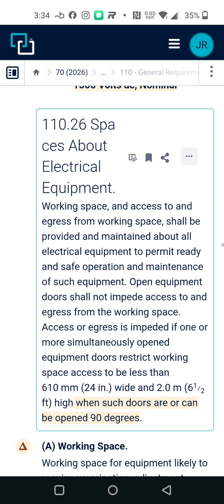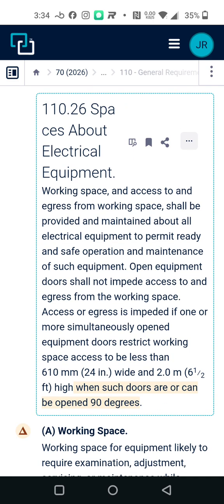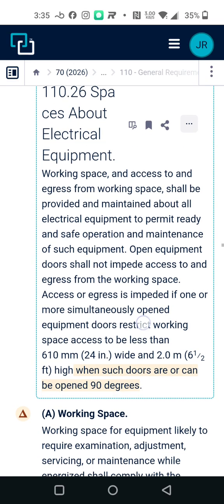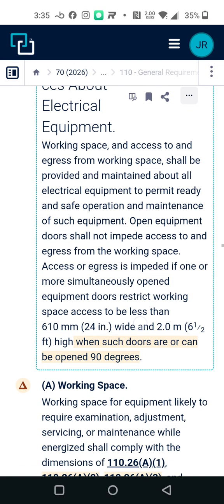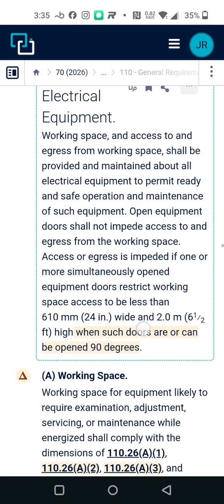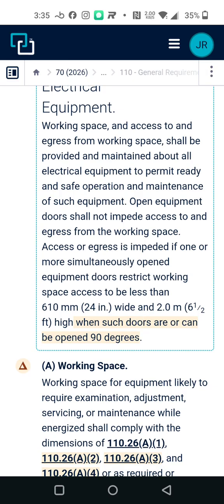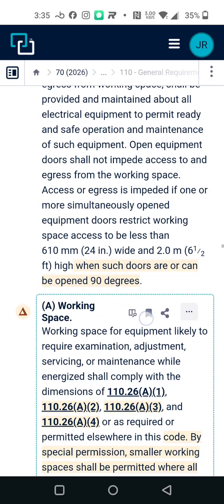Spaces about electrical equipment. Working space and access to and egress from working space should be provided and maintained about all electrical equipment to permit ready and safe operation and maintenance of such equipment. Open equipment doors should not impede access to and egress from the working space. Access or egress is impeded if one or more simultaneously open equipment doors restrict working space access to be less than 610 millimeters or 24 inches wide and 2 meters or 6.5 feet high, when such doors are or can be open 90 degrees.